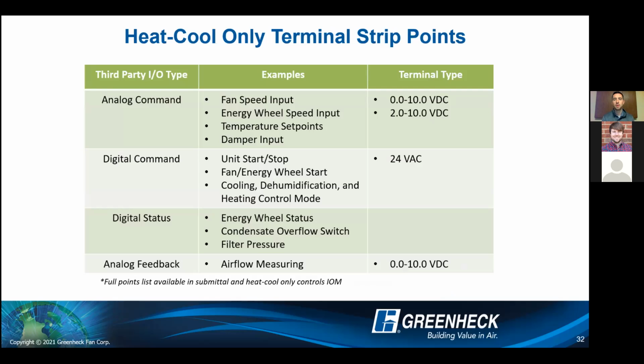So this is an example of some points that you would see. As an example, there's some different analog commands, digital commands, different statuses that we may provide from our controller back, or from relays back to the terminal strip, that you can read with that third-party controller. Obviously, there's a lot more to this list. And if you have any questions, again, reach out to Holden. We can make sure you have this list. But I will say this is a great option for any time you want a third-party controller, but it's still allowing us to make sure that we're in safe operating ranges with all of our cooling and heating.